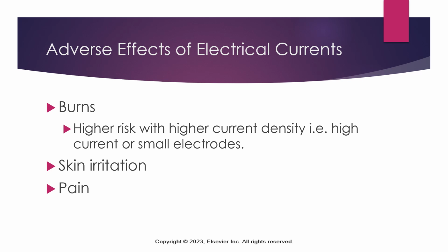So if you're using really small electrodes, this is something that we talked about in class, there's a higher current density going through those small pads. So you want to be really cautious not to turn the intensity up too high or anything along those lines. And any form of skin impedance that you can eliminate would be best. So make sure that you clean the skin either with an alcohol pad or a damp towel to remove any oils, lotions from the skin, as that can increase skin impedance, and we don't want that.